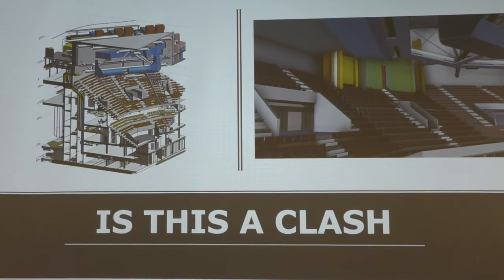We left quite often in the model, and some people, not everybody, got upset with this. We left clashes on purpose, so that looks silly, doesn't it? Obviously, services running up through the back of a set of bleachers. Yeah, it looks completely silly. But the reason why it was left is because it took ages for eventually the architect and the structural engineer to get round to giving the void and bringing this whole structure down the stairs to a point where you could run the services through.